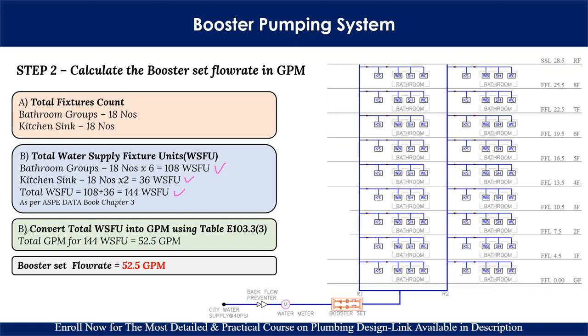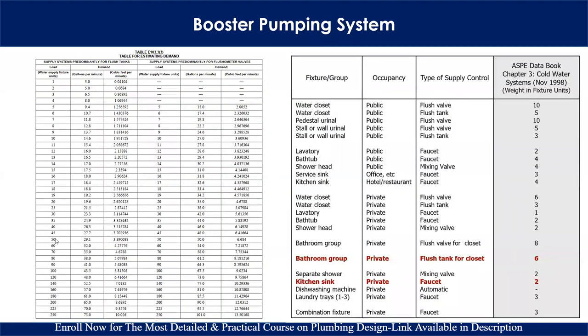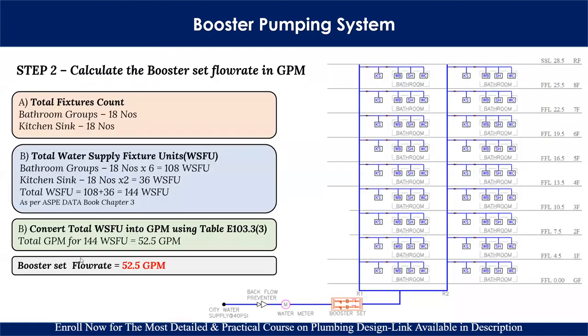The next step is to convert 144 WSFU into GPM using table 103.3. Looking at the table, we have values at 140 and 160. For 140, the flow rate is 52.5 GPM. So for 144 WSFU, the total flow rate is 52.5 GPM. This means the booster set flow rate will be 52.5 GPM. This completes step two.